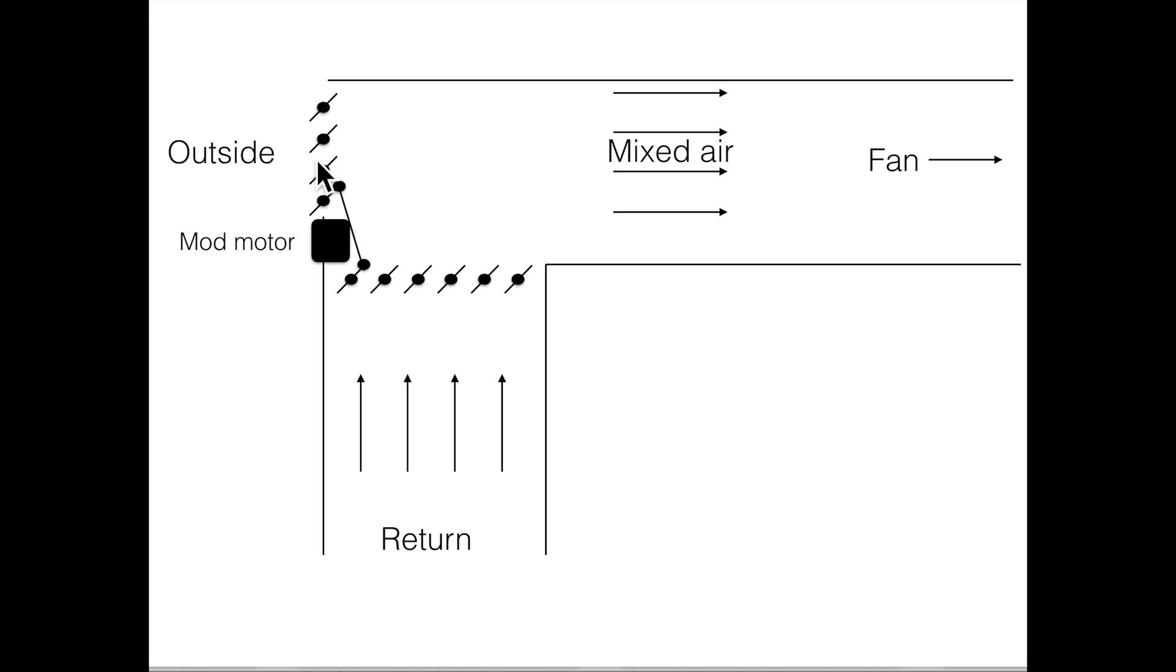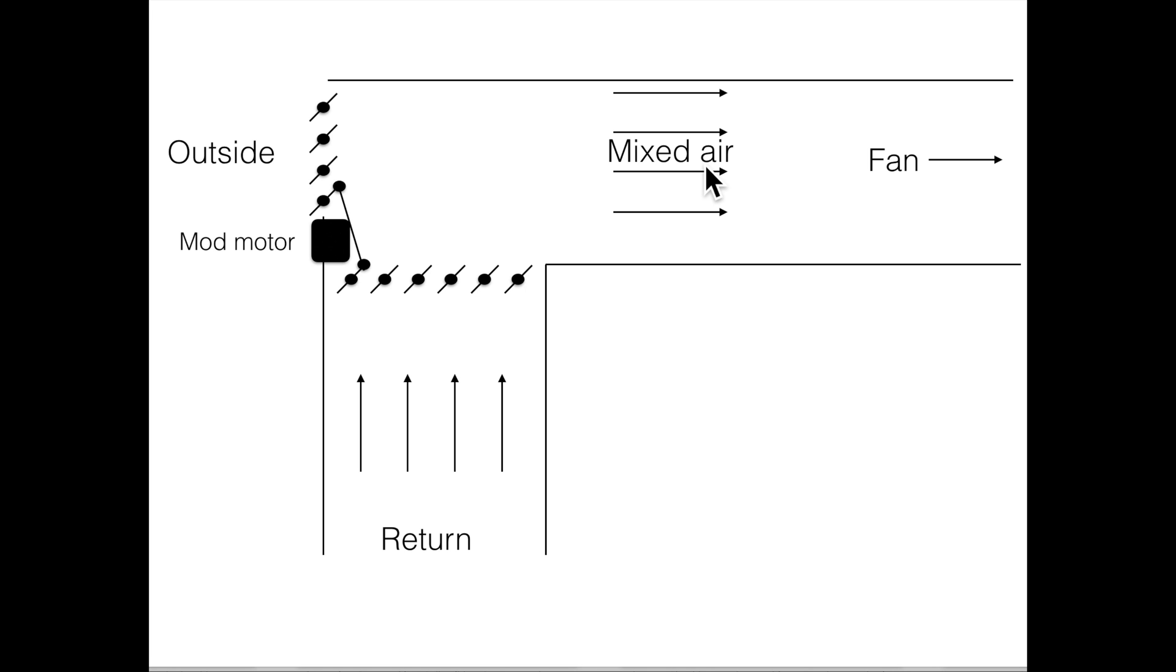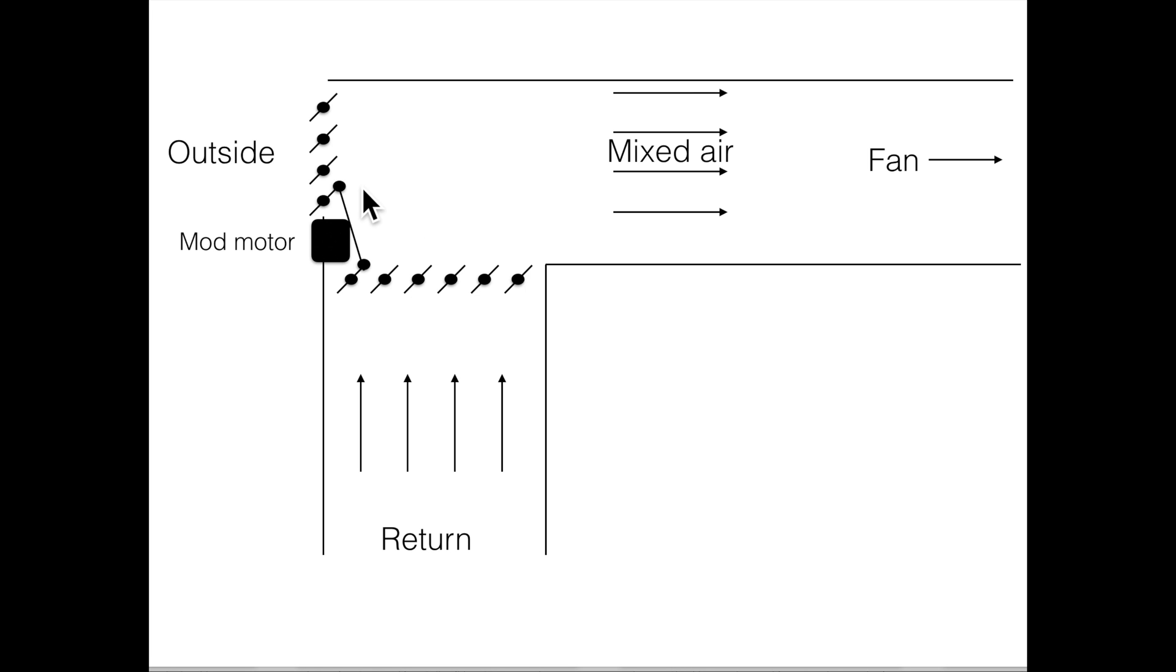Now as I pull outside air in, I'm going to be pulling less return air in depending on the damper position. I am going to increase the pressure inside the structure because I'm taking outside air and I'm putting it in the structure. So there can be a problem there, it can start opening doors and things like that and causing some problems in the structure if this isn't dealt with.